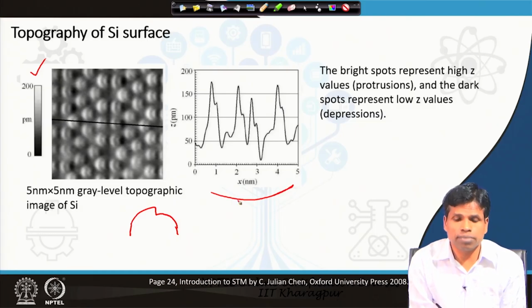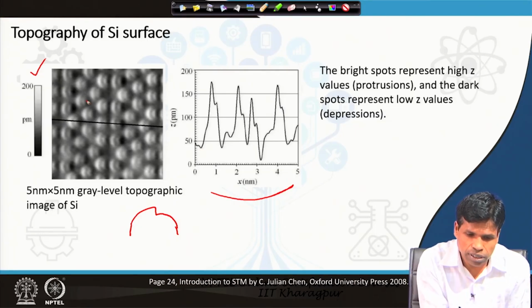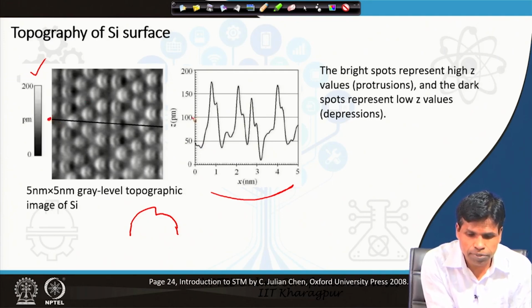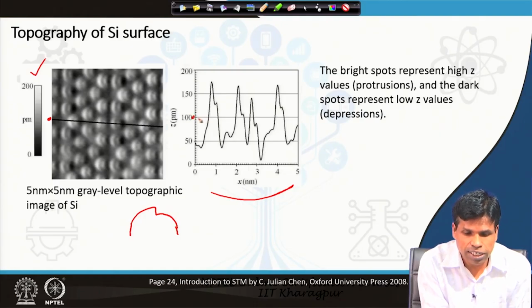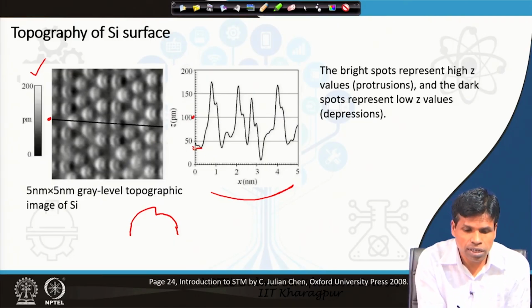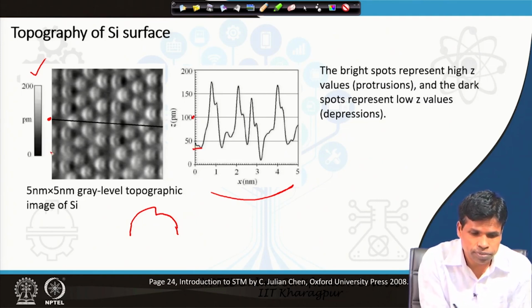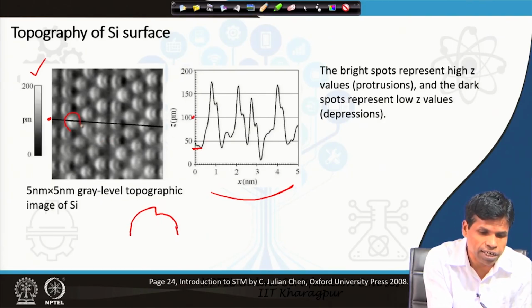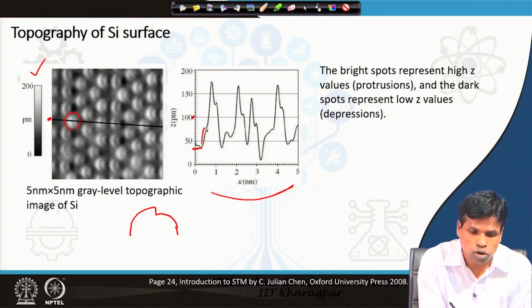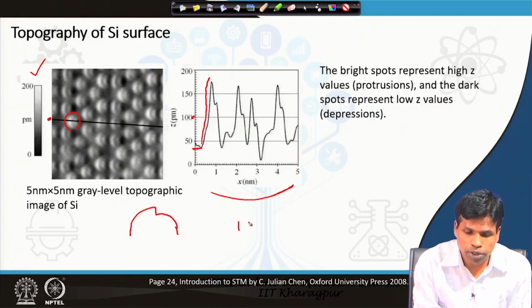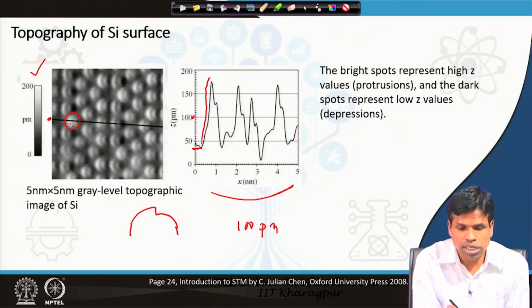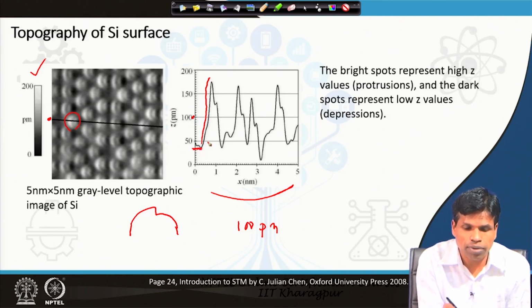The line scan graph gives us quantitative information. As we can see here, it is beginning from here. This region looks darker, which means the height is low, it is in a depression, and that would measure a small current. This is around 70 picometer downwards, and then as soon as a brighter portion comes, which is an upward portion or protrusion, the tip has to go upward, and it has gone upward around 50 to 150, a height of around 100 picometer. The height of this sphere is 100 picometer above the ground level, and then it has come down.